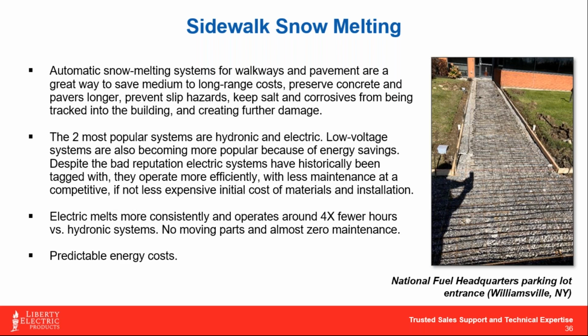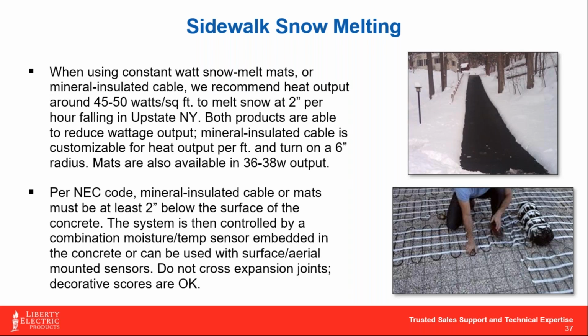can operate far fewer hours versus the hydronic system because we don't need to continually cycle glycol and keep it moving. Many times these electric systems just come on or off as needed. And because they ramp up their temperature so quickly, generally we can heat the sidewalk, melt it, run the timer until it actually dries the pavement, and then the system will shut itself off. So typically here in upstate New York, if we're speccing at around 50 watts a square foot, that's good enough to keep up with 2 inches per hour falling. So that's pretty good pace.